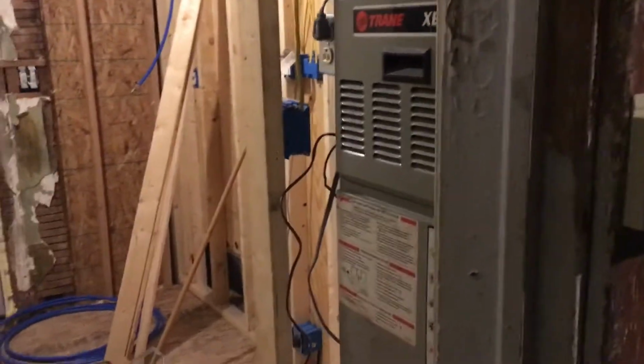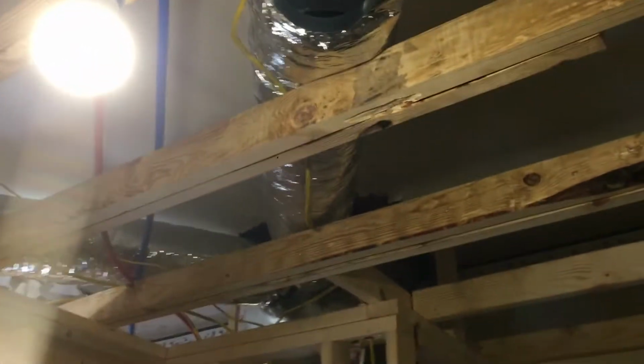Alright, it's Tuesday. The mastic on the ductwork should be cured so he can finally run the system. Right now I've just got the fan running to test the airflow, and we've got good airflow. This thing is just dumping air on me. I can stand under that duct, under this one, and I'm just getting showered with air. Same thing in here. If I stand under this one, I get a nice blast of air dumping right down on me.